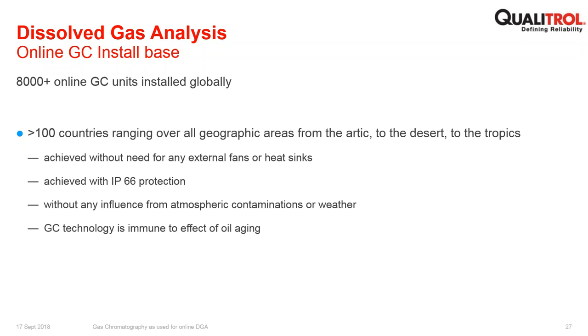And GC technology is immune to the effect of oil aging. So as transformer oils age, they don't just produce these 9 target gases. They produce many, many other gases, many other volatile compounds in the oil, alcohols, for example. Gas chromatography does not see these because it physically separates the components before sending to the detector. It is immune to the presence of other contaminants in the oil.